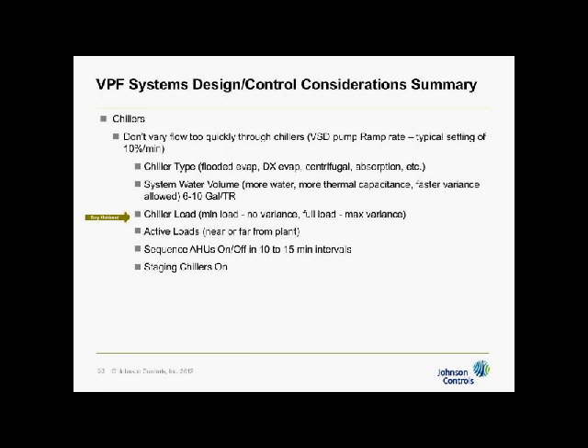The chiller's load changes what the rate of change is. If the chiller is fully loaded, it can handle its maximum change, whatever that might be. If in a given system 20% happens to be maximum, then it could handle 20% at 100% load, but when you're down at 10% load or min load, it'll literally shut off if you lower flow. There's no place for the vanes to go. They're fully closed. They can't close anymore.